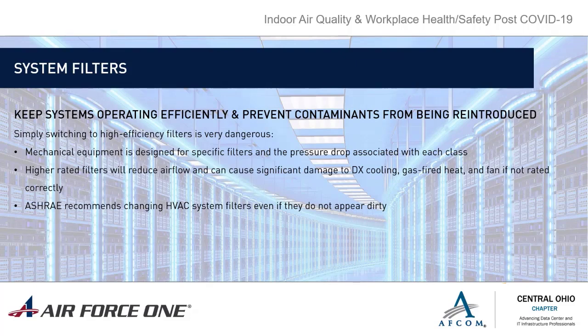When you start talking about gas heat, or more specifically package DX, which a lot of data centers have, you're reducing the feet per minute across your evaporator coil, and it starts wreaking havoc on your compressors, your TXVs, and the entire refrigeration cycle. It could cause cycling, and at the end of the day, if you don't have the proper airflow, it's a trickle-down effect. Every part of that piece of equipment could be at jeopardy of failure, or a higher rate of failure, because you're not moving the proper air.